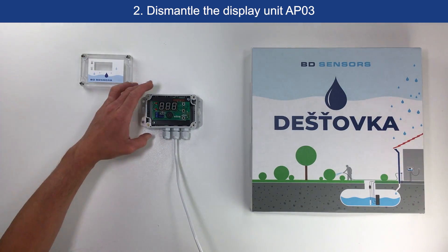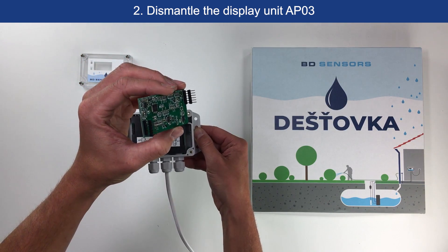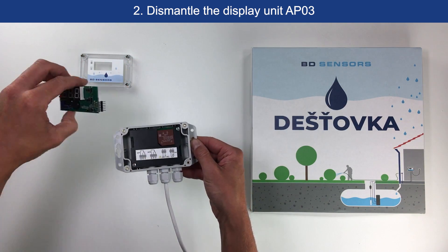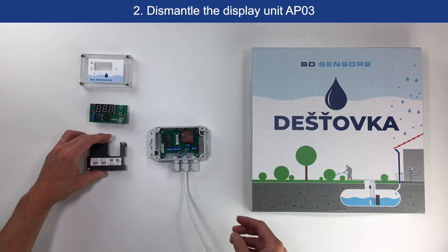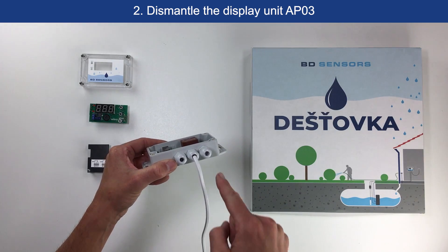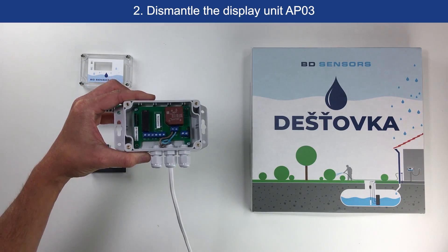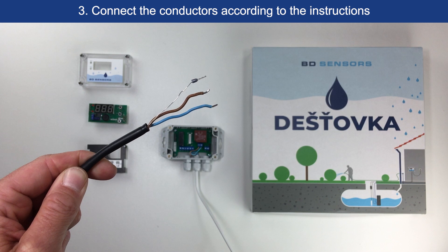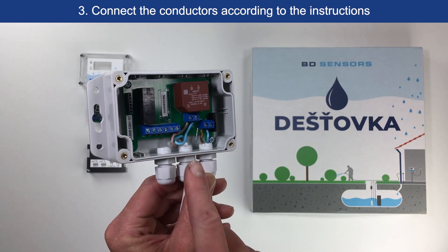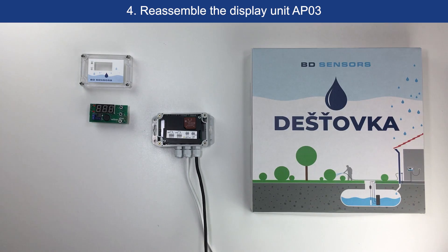We dismantle the display unit AP03. Remove the board with the display and connectors, then remove the cover of the bottom plate with the wiring diagrams of the switching outputs. Now we have the unit ready to install the connection cable through the cable gland. Pay attention to the correct connection of the cable conductors to the respective terminal blocks. In addition to the blue and brown connectors, the connecting cable also has the previously mentioned shielding conductor — it does not connect on the display unit side. Here we can see the correct connection of the wires in the display unit. After connecting the wires, we assemble the whole unit together in the reverse order.